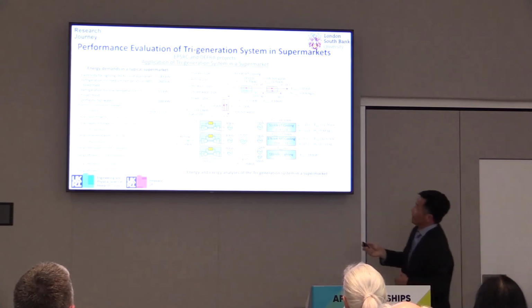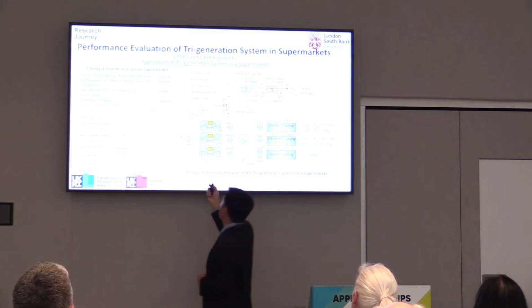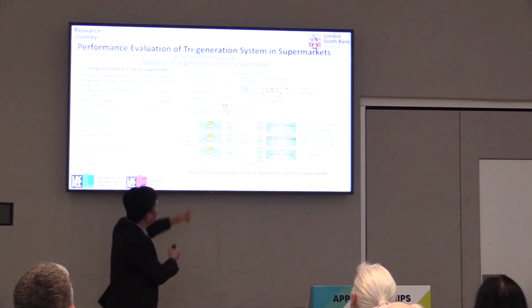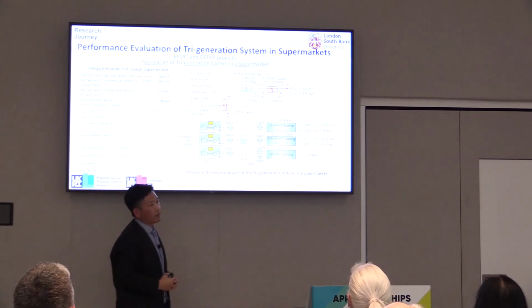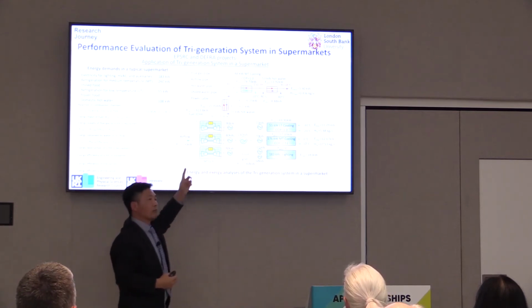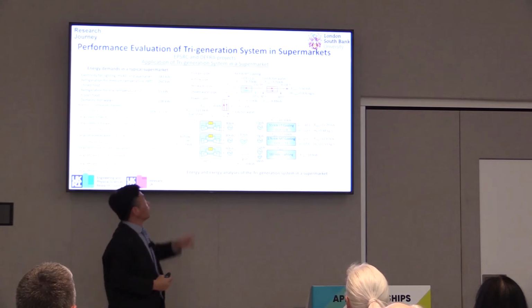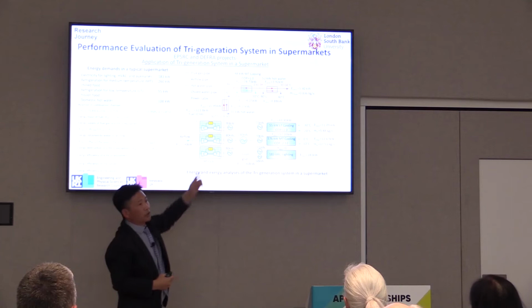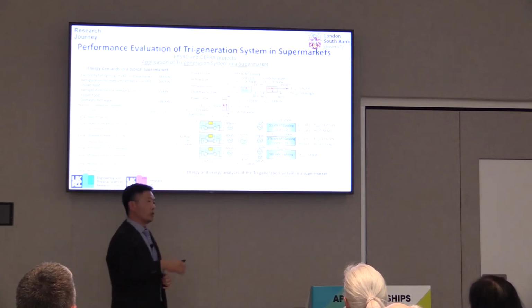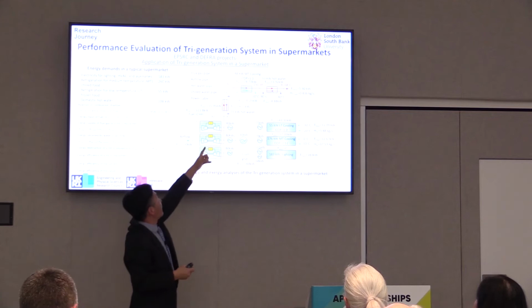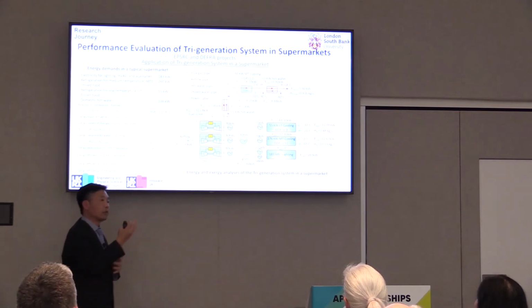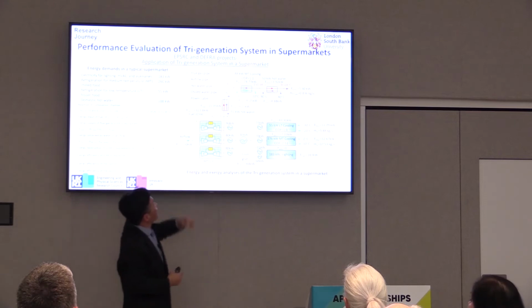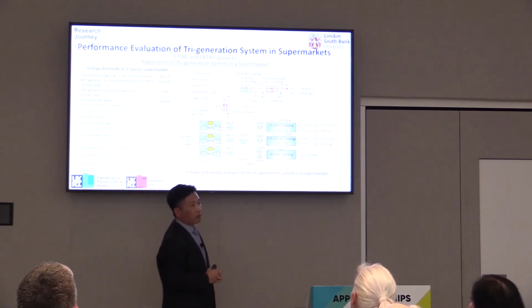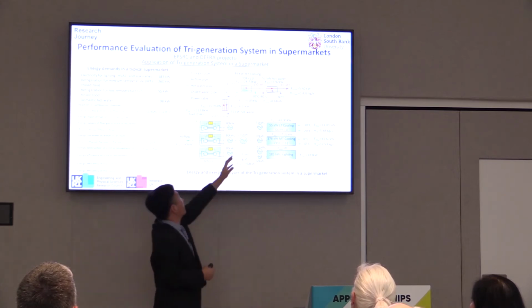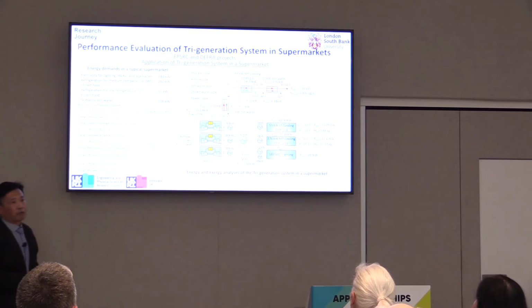And in the meantime, we have some exhaust heat here from the turbine exhaust. The temperature we calculated is about 300 degrees C. So we designed 2 heat exchangers, one used to produce the domestic hot water, and another an absorption chiller, because we have the exhaust heat, to produce the rest of the medium temperature cooling. If you add this cooling, the domestic hot water and the electricity together, they can exactly meet the energy demand of the supermarket.